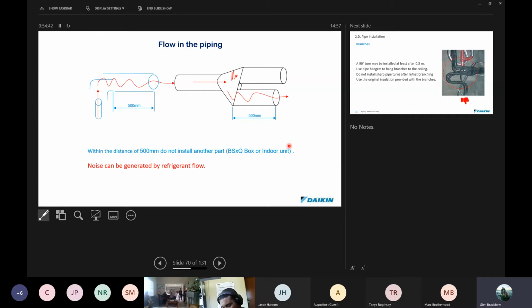Another reason for using RefNets, and in particular on indoor units, is that when installed correctly, they reduce the noise of flow through the pipes, because they break the flow up evenly. It's something you won't get with a T-joint. You'll get quite a bit of noise as the gas swishes around through all those bends. So we're breaking down and getting rid of the turbulence that can be created, and that will always show up as noise.